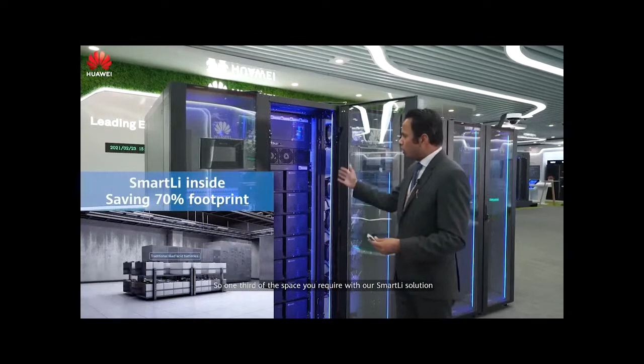Compared to lead-acid batteries, which are vulnerable to thermal runaway and can even catch fire, the material for lithium batteries is LFP. This LFP material is less susceptible to catching fire in case of thermal runaway, and we have 3 levels of BMS in these batteries: module level, rack level, and system level, ensuring comprehensive visibility and capability.